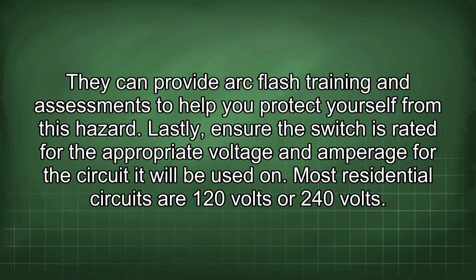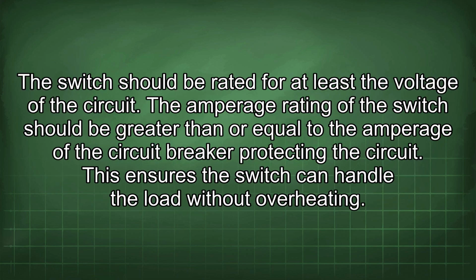Most residential circuits are 120 volts or 240 volts. The switch should be rated for at least the voltage of the circuit. The amperage rating of the switch should be greater than or equal to the amperage of the circuit breaker protecting the circuit. This ensures the switch can handle the load without overheating.